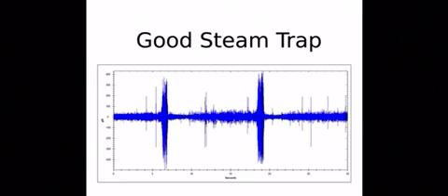Here's a dynamic signal of a good steam trap. It's doing exactly what I expect from a steam trap. It's collecting the condensate. It's opened when it's time to purge the condensate and bad gases. It purges here, and then it closes again so that the cycle can repeat itself. Again, simple. A valve with an IQ of 1.